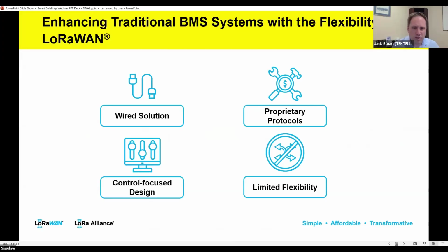I want to first talk briefly about some common challenges with traditional BACnet-based systems. These are most often based on wired solutions, which can limit where you install devices and add complexity, time, and cost for installations in both new buildings and existing infrastructure. These solutions are usually proprietary and not always easy to expand, and they were primarily designed around controlling buildings, not necessarily data insights. But I want to be clear these are not flaws—they're just limitations that made sense in the context of when they were built.